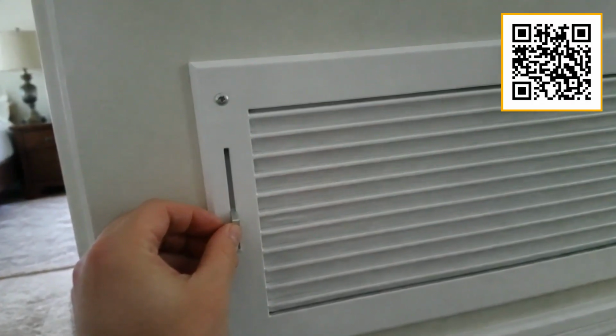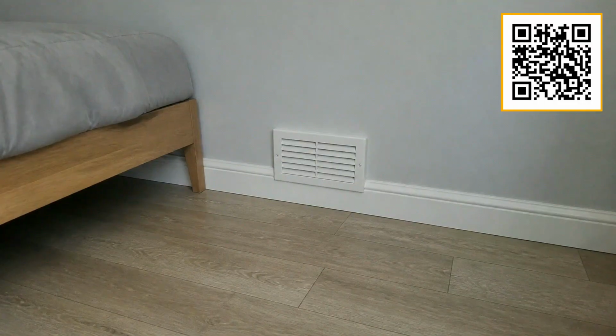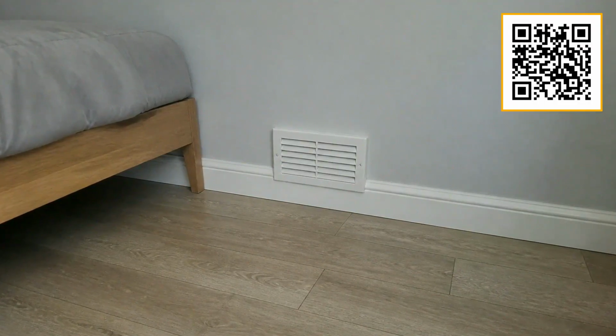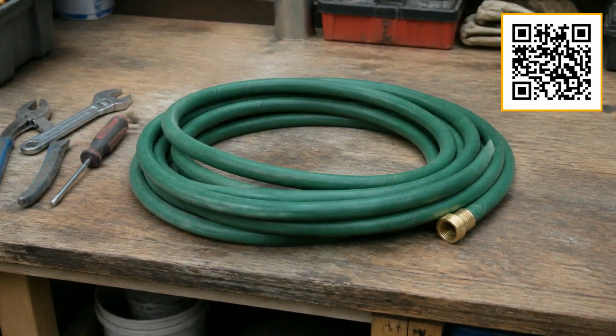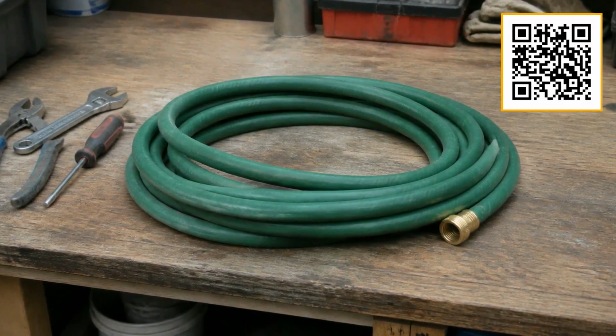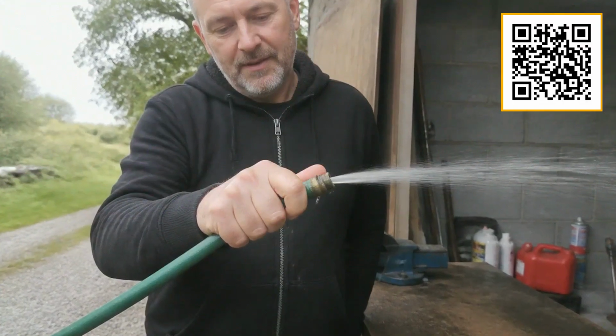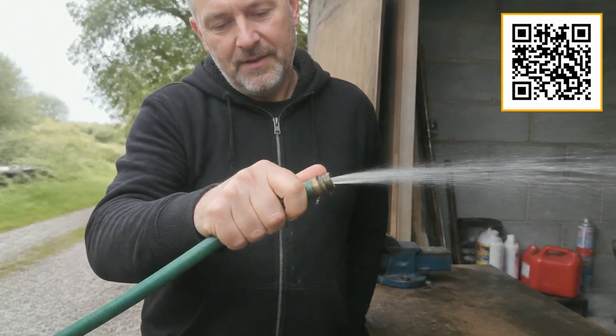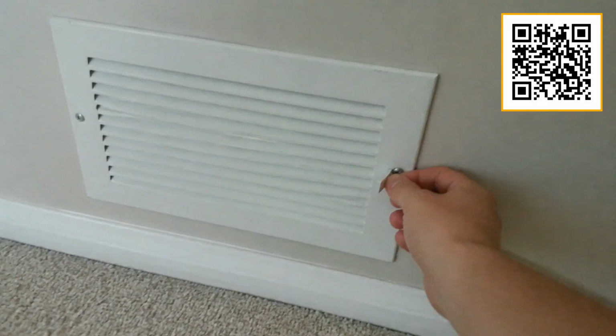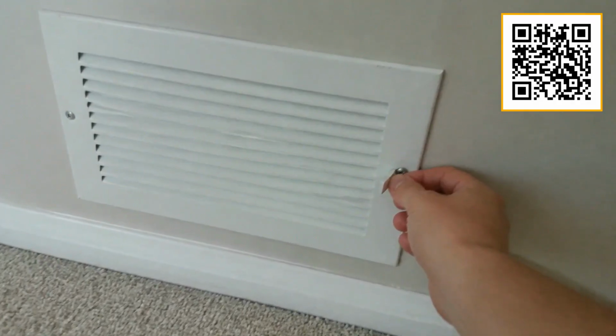Now let me push back on the logic you're using. The reasoning makes intuitive sense. Why heat or cool a room nobody is in? But your HVAC system does not work like a garden hose where you put your thumb over part of the nozzle and less water flows. It works like a pressurized loop with a pump that is always moving the same volume. Blocking part of the output does not reduce the load. It redirects the stress into other parts of the system.